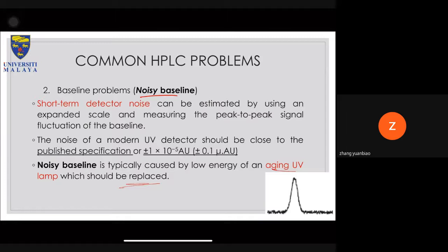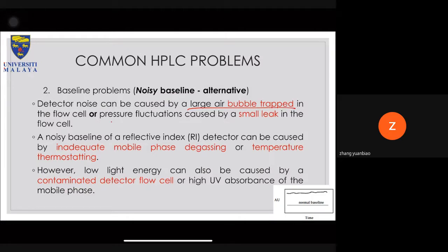Alternatively, detector noise can also be caused by large air bubbles trapped in the flow cell, or pressure fluctuation caused by a small leak in the flow cell. So why the flow cell? Because the flow cell affects the chromatogram, which is the baseline. Okay? A noisy baseline in a refractive index detector can be caused by inadequate mobile phase degassing or temperature thermostating. However, low light energy can also be caused by a contaminated detector flow cell or high UV absorption of the mobile phase. Okay, so these are some other examples.